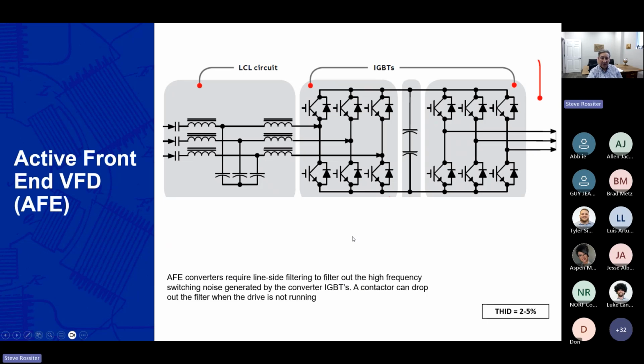Active front ends have been traditionally a very expensive technology because you're basically taking the one variable frequency drive and almost adding another, and usually the cost has been almost the same as 3 regular 6-pulse VFDs. But what you're doing now is taking the same inverter section that converts the DC back to AC, but your converter section is now an active device. So rather than being diodes and rectifiers, these are active devices that you can now fire in any particular pattern for what your objective is, which could be optimizing harmonics.